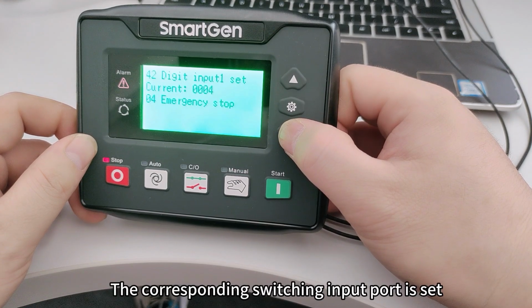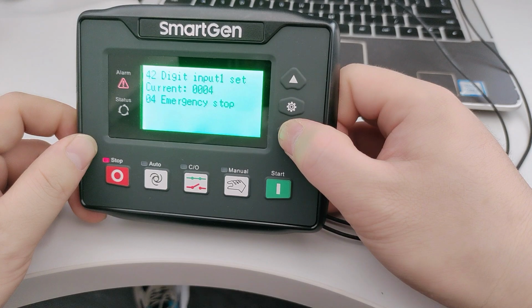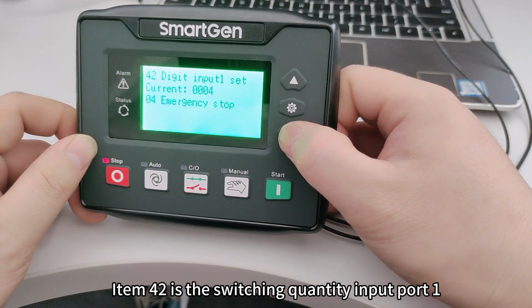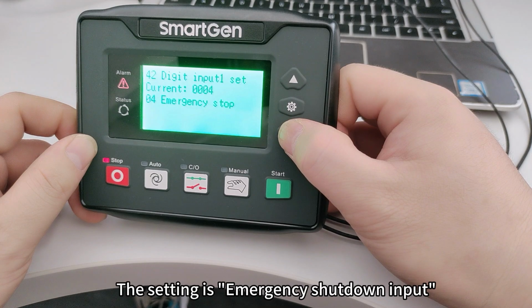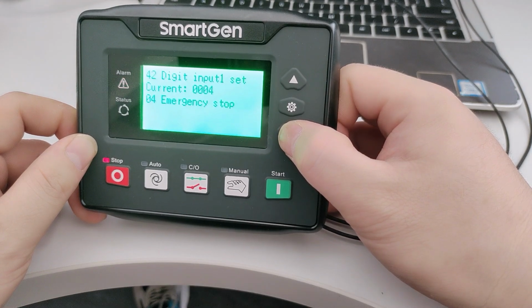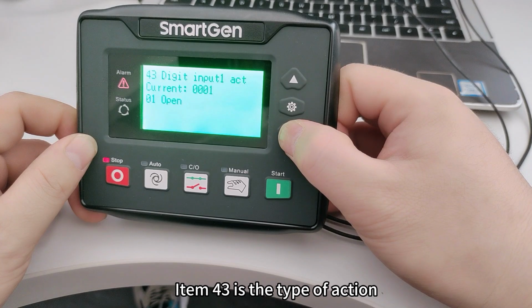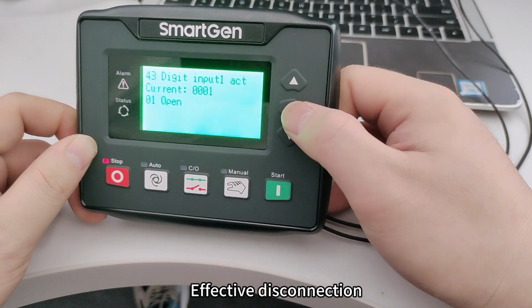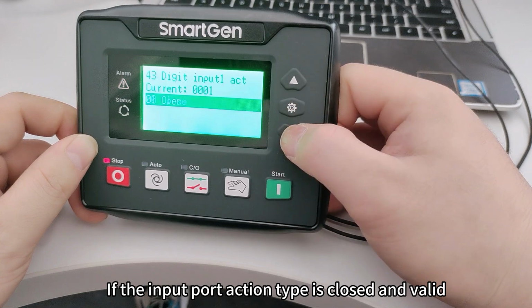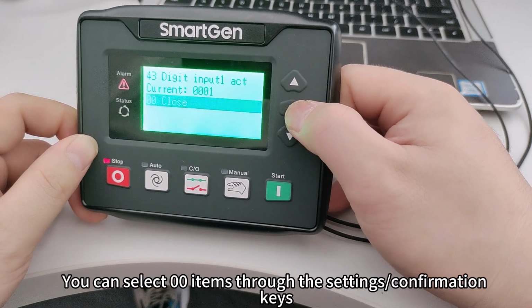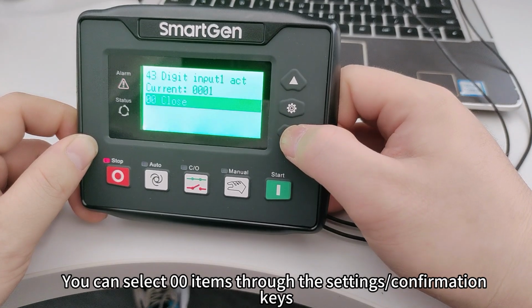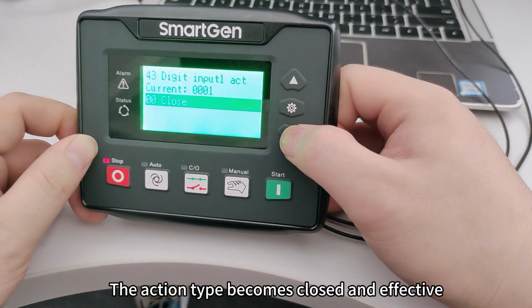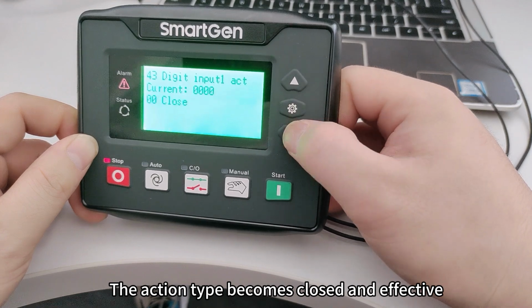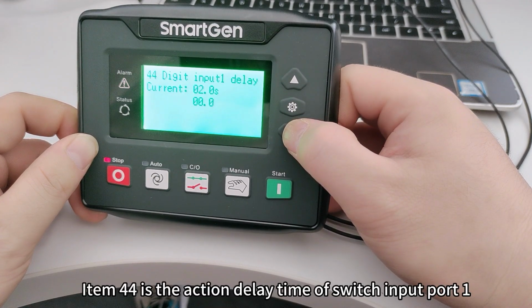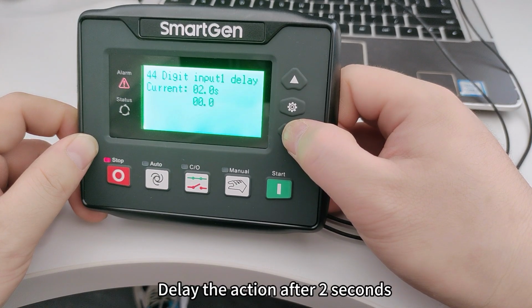The corresponding switching input port is set. Item 42 is the switching quantity input port 1. The setting is emergency shutdown input. Item 43 is the type of action, effective disconnection. If the input port action type is closed and valid, you can select item 00 through the Set Confirm key, so the action type becomes closed and effective. Item 44 is the action delay time of switch input port 1. Delay the action after 2 seconds.